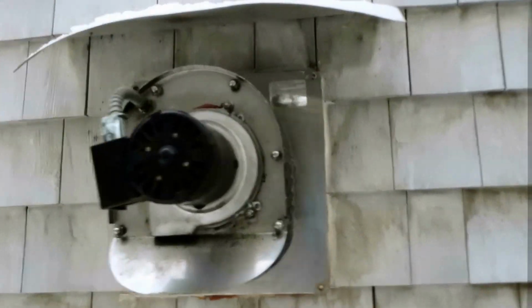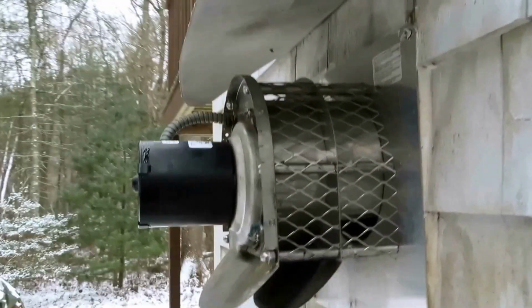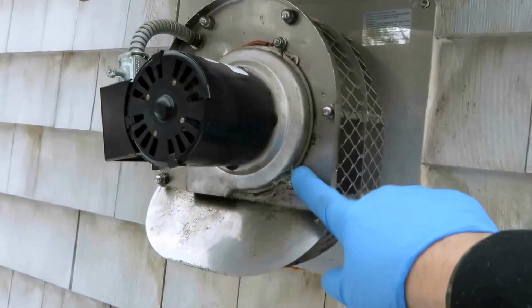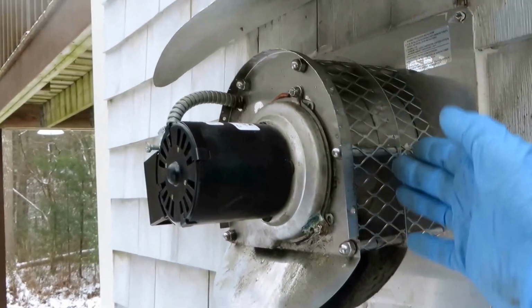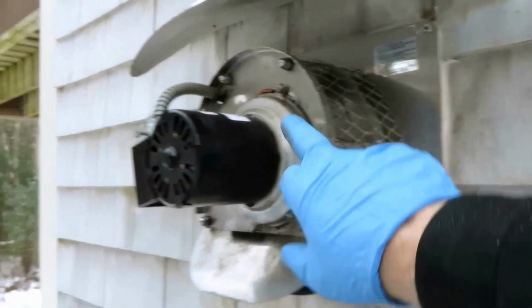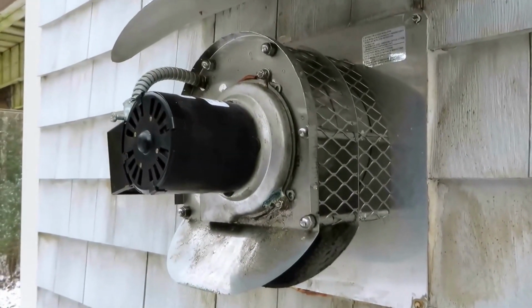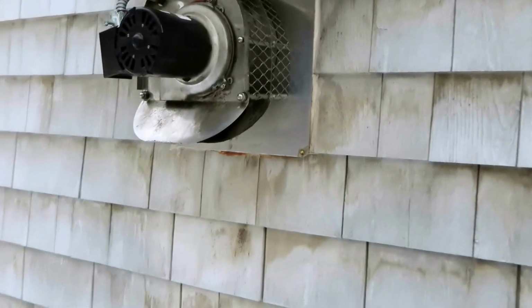But. No grinding. So that probably did it. Just see what I did was I moved it out a little bit. Because what happened is the fan blade in there, if that fan blade's too close, it was grinding. This way here, moving that out is going to stop it from grinding. Either that or you put a whole new motor assembly in there, and that's not really too feasible here. Brand new unit. Yeah. Okay, so I'll button this thing back up, and I think you're going to be good.